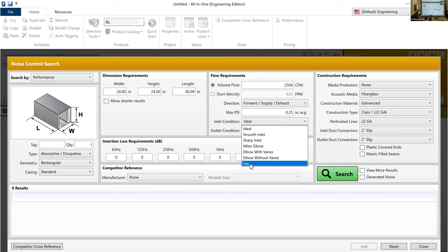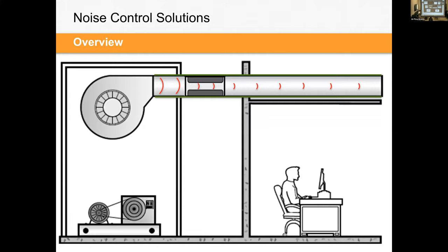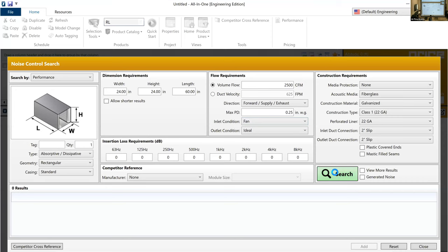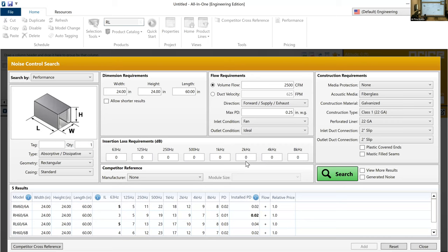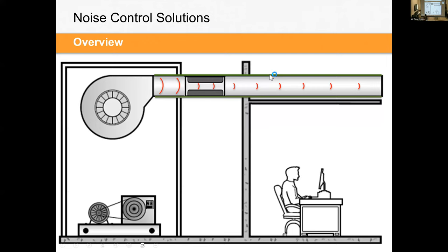When it's not the case, you can do things like add a fan. If there's a fan directly at the inlet, very similar to the PowerPoint that I had here, you can select that inlet condition. When you search for your silencer based on those parameters, it's actually going to apply that system effect pressure drop, and you can see that here. I'd say you always want to be aware of that and try to maintain those values when possible. But when you can't, then apply them when you make the selection, so you're allowing for those increases.